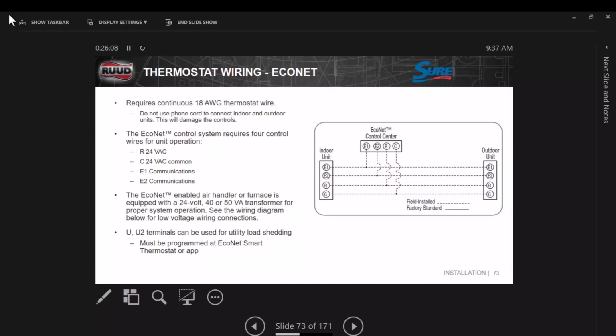But here's your typical setup for an Econet system right here. Econet control, Econet inside, Econet outside. So if you're going to put an Econet control with any of these mid-tier units, except for the heat pump on the 15 SEER, this is your wiring schematic. That's all the wires you need. On the board, you can also see what we call load shedding terminals for the utility, U and U2. In areas around Texas right now, like Austin and some of the big metropolitan areas, they want that control. At the very inopportune time, like when it's really hot or you really need the air, they're going to turn it off, right? Because we don't have enough power to supply the grid.